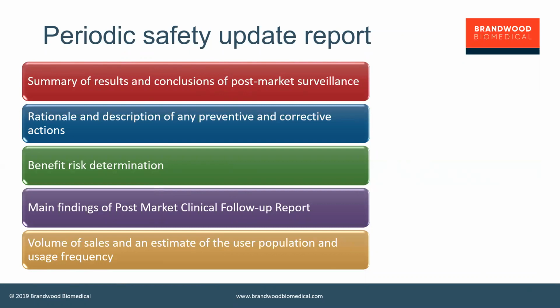Absolutely. So there are two things I'll mention here. One is this is the same kind of content, and again, you mentioned it earlier, there's a lot of overlap. This is the same kind of content that you would expect to put into your clinical evaluation report on your periodic review and your updates of that. So it's not completely unique. But at the same time, this is a significant undertaking, and we need to make sure that manufacturers are doing these risk determinations and this trending, because before, the notified bodies and the competent authorities were doing that assessment. Now they're putting the onus on the manufacturer to do that for them so that they can have a better scope across all of the medical devices as to how these devices are performing over the term of their use.